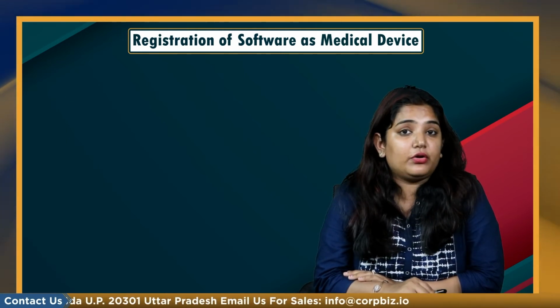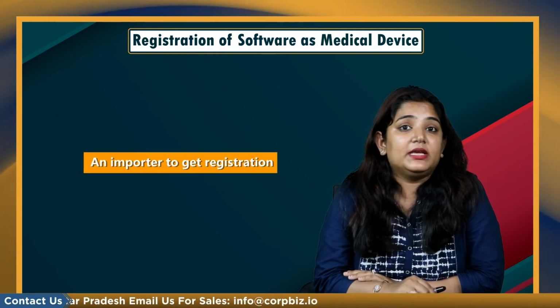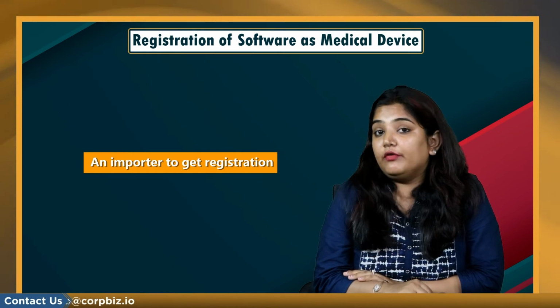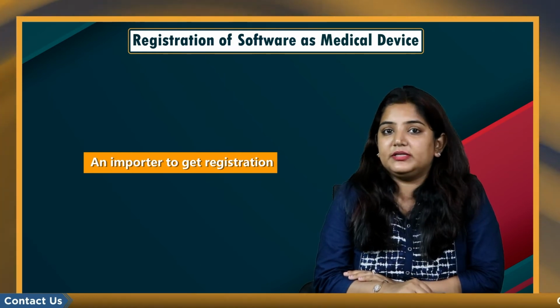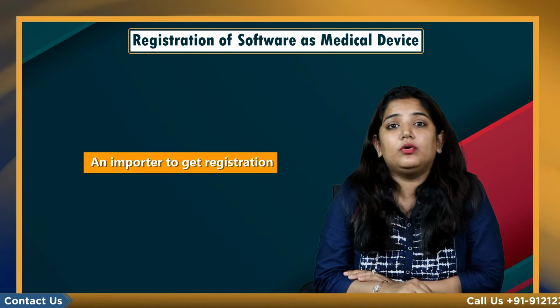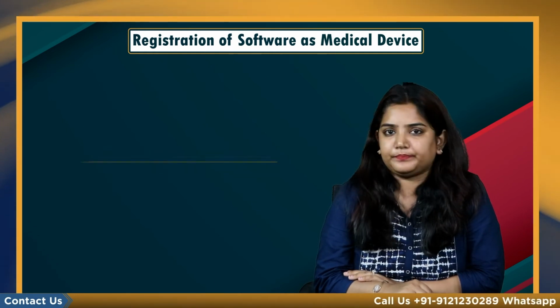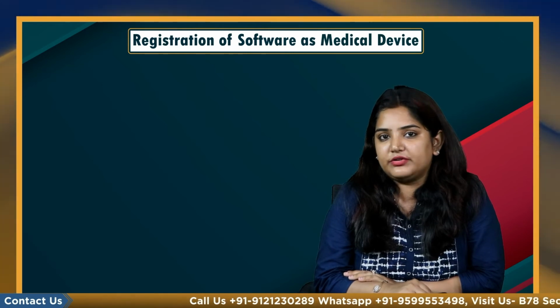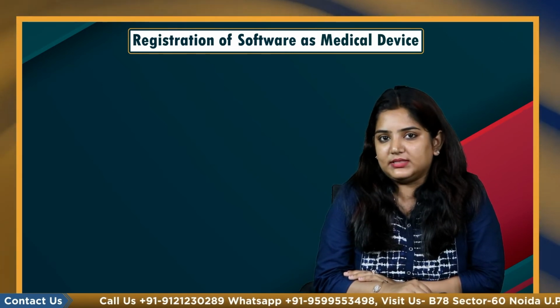A manufacturer or importer of medical devices is the one who can apply for the registration of such devices. For an importer to get registration, it is a prerequisite to have a wholesale drug license. However, CDSCO is currently permitting registration without such a license.